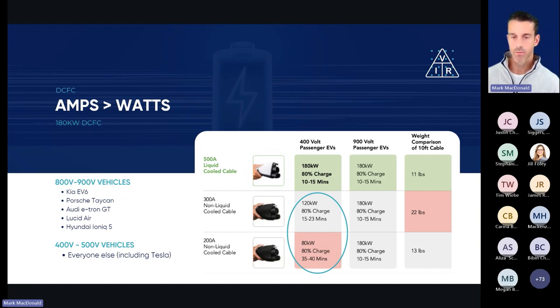...the total power I can draw is a function of the cable amperage and the battery voltage. So if we take, for example, a 180 kilowatt charger supplied with a 200 amp cable, when I plug that 200 amp cable into a 400 volt battery, even though the charger is rated at 180 kilowatts, going back to Ohm's law, it's 200 times 400 - I'm only ever going to pull 80 kilowatts.